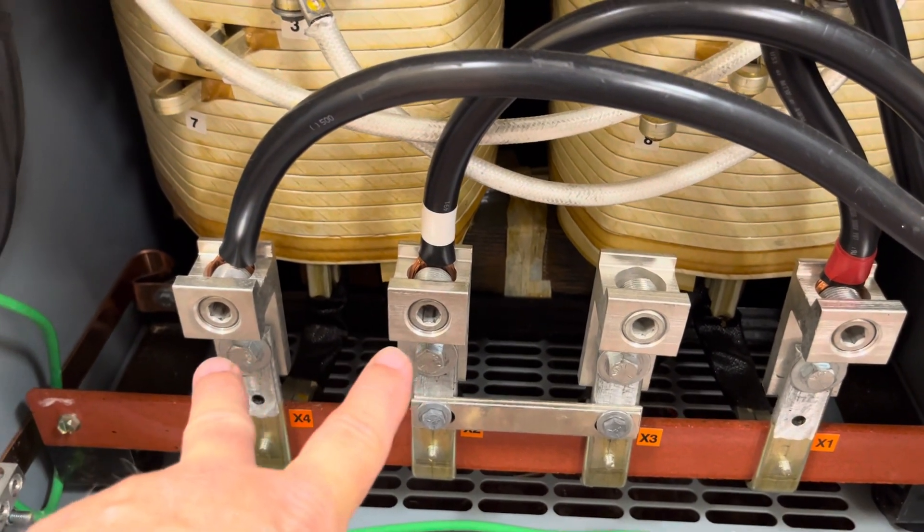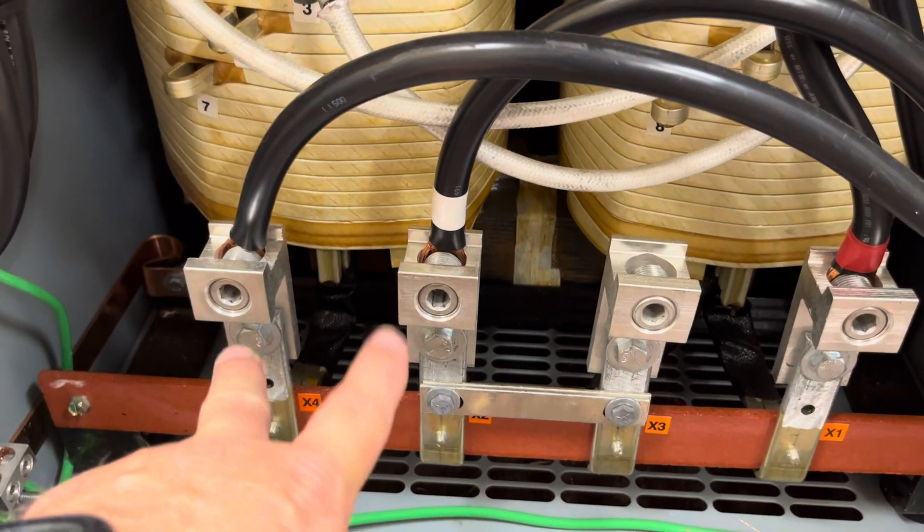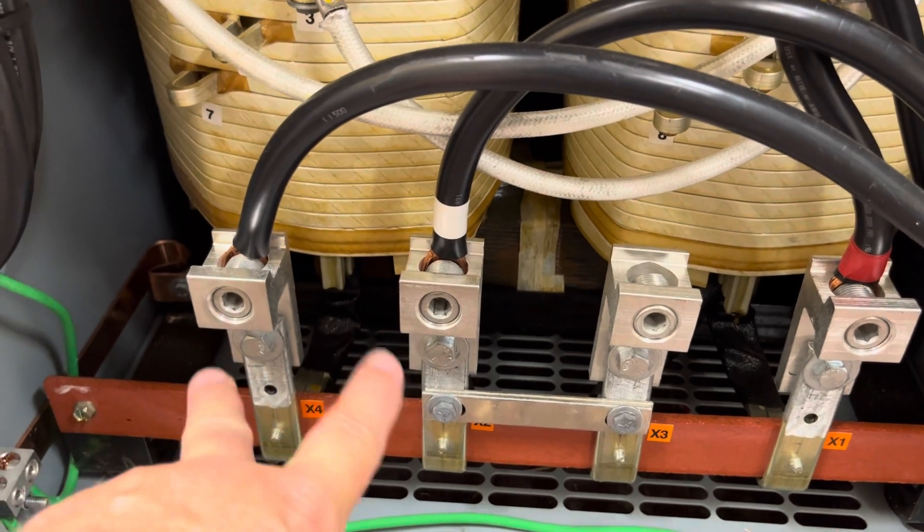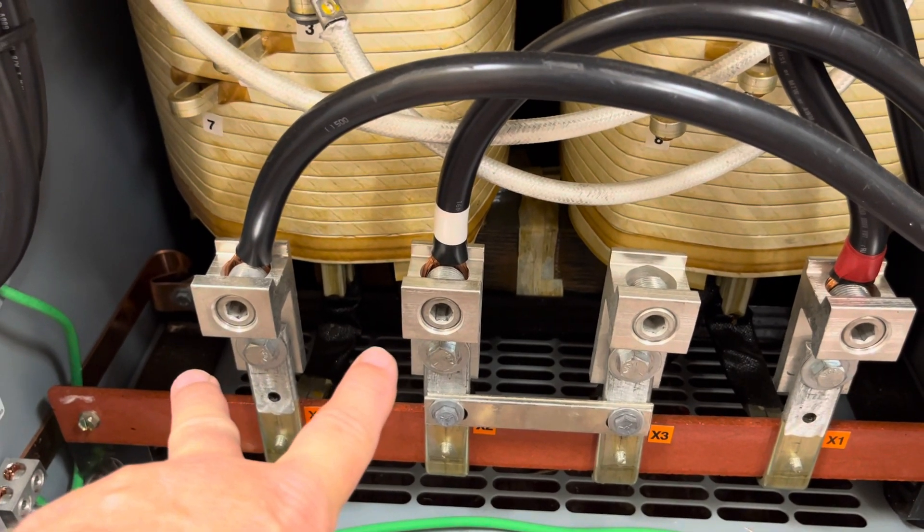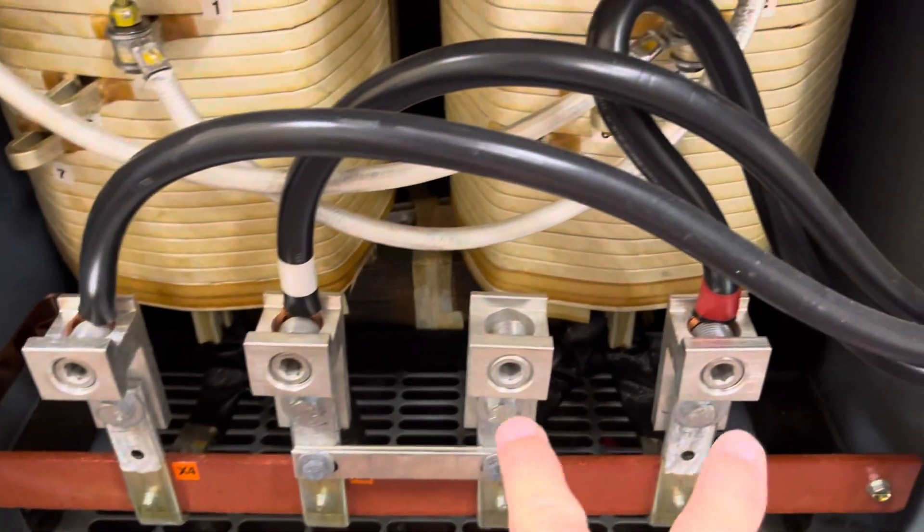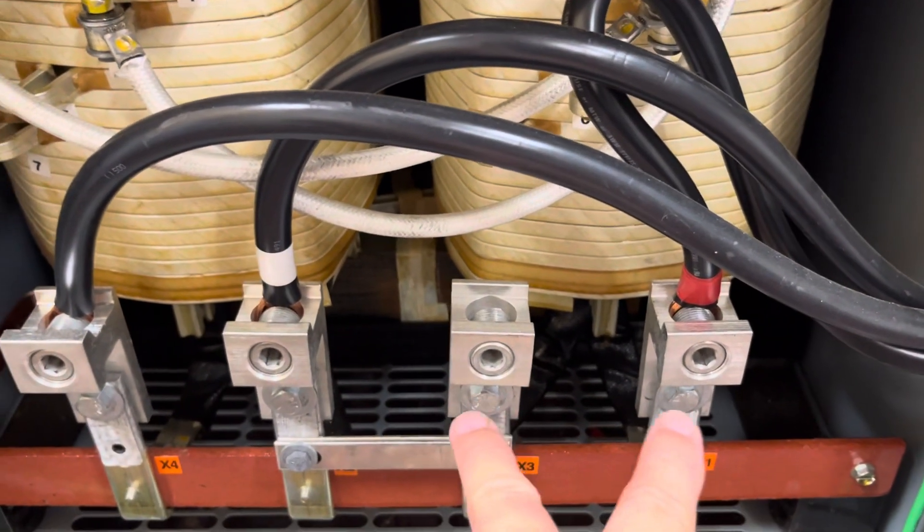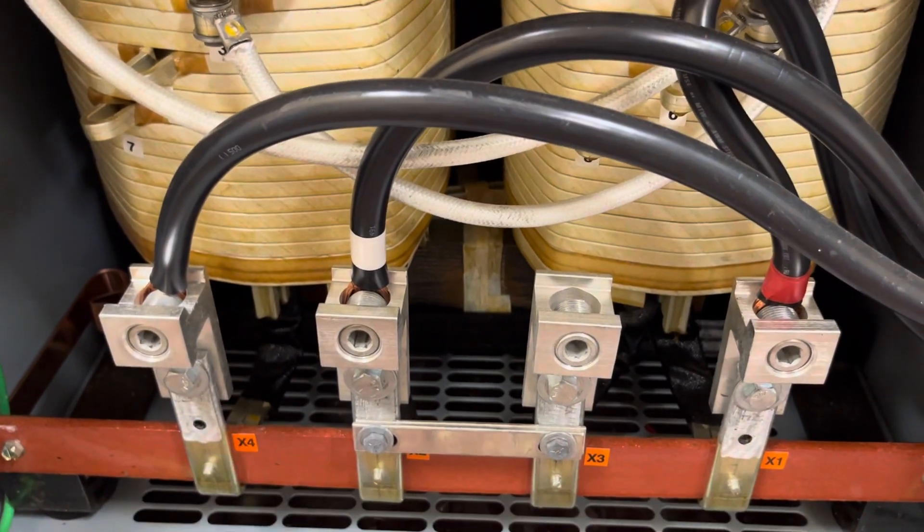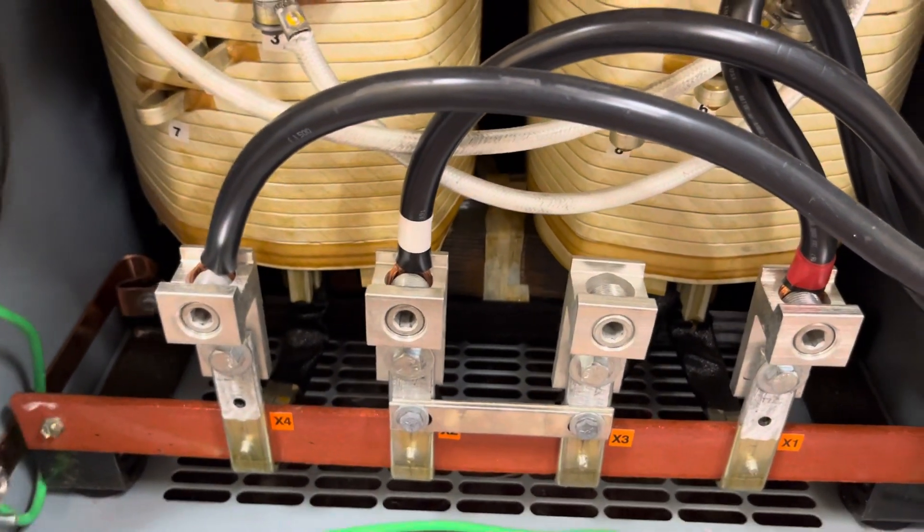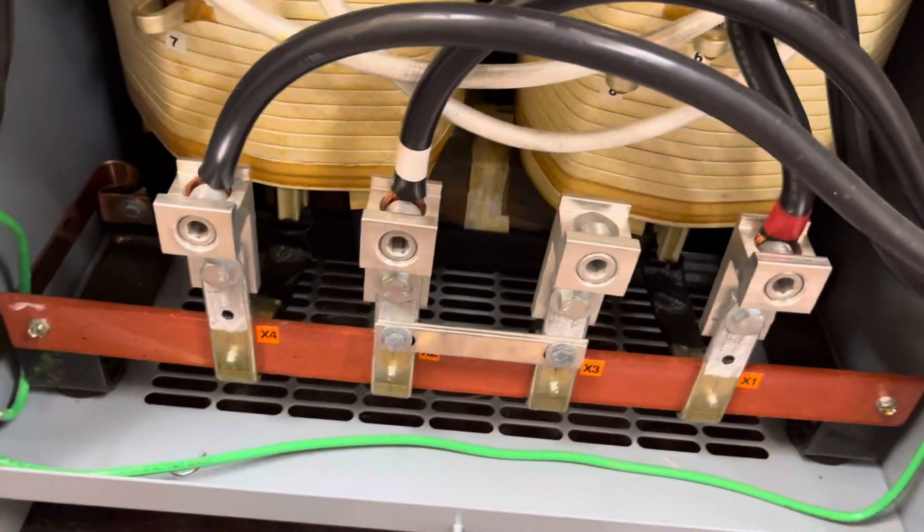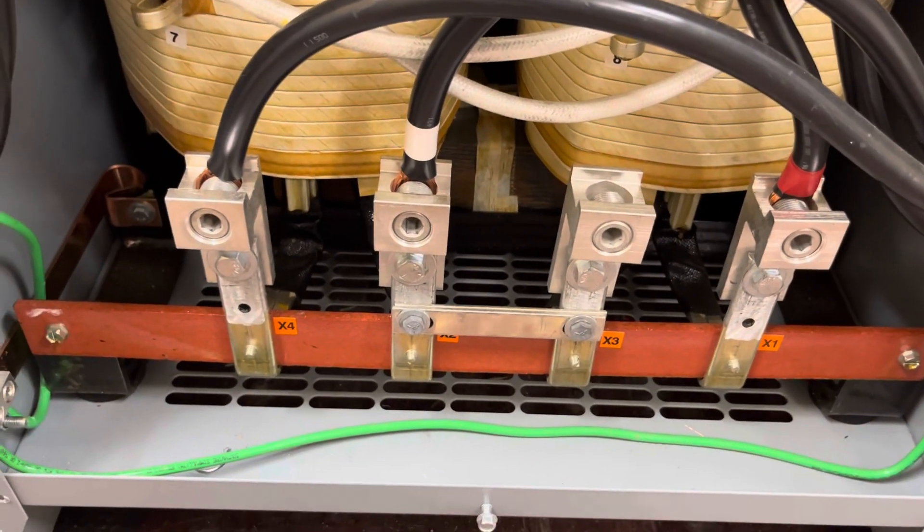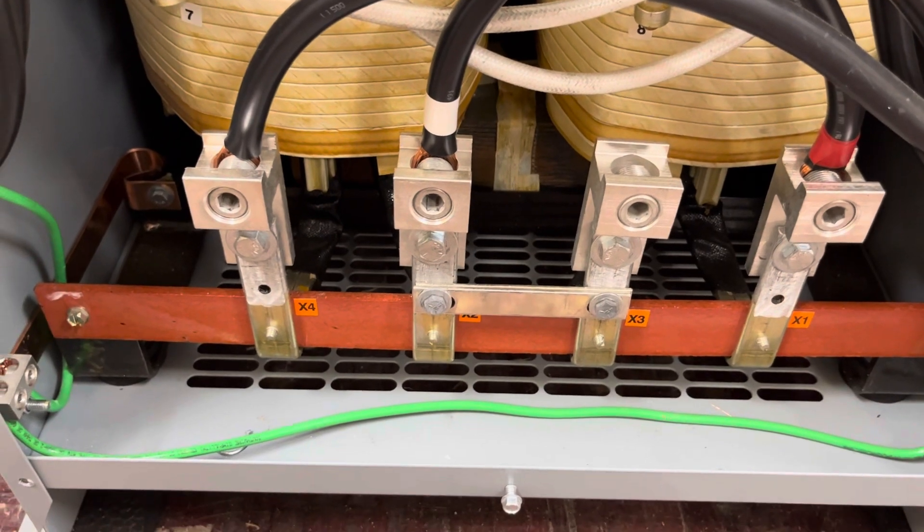So there's 120 volts from here to here. Now this is all dead, so don't worry about that. 120 volts from here to here. 120 volts from here to here. And 240 volts across. So this is where I'm picking up my neutral.